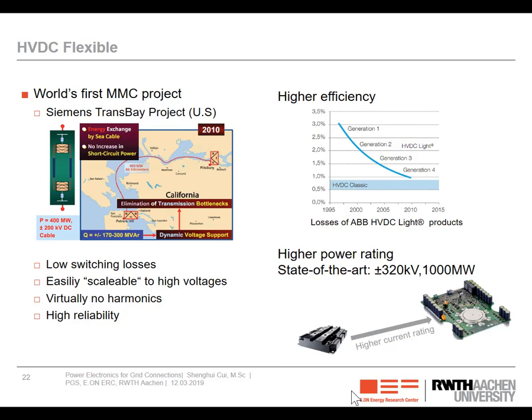Today, the trend is that both the voltage rating and the power rating are going higher and higher. Currently, the highest VSC HVDC project in operation is plus minus 320 kV, 1 gigawatt. As far as I know, there is also a project under construction with a voltage rating of plus minus 800 kV and a power rating of 5 gigawatts. So both the voltage rating and the power capacity, as well as the efficiency, are already comparable with the classical HVDC technology.